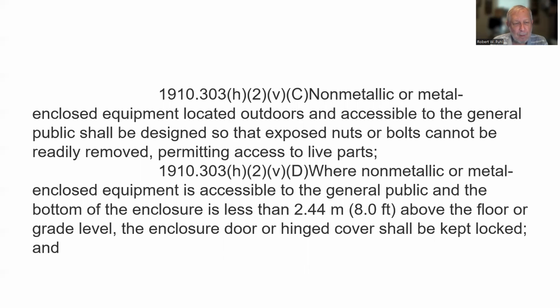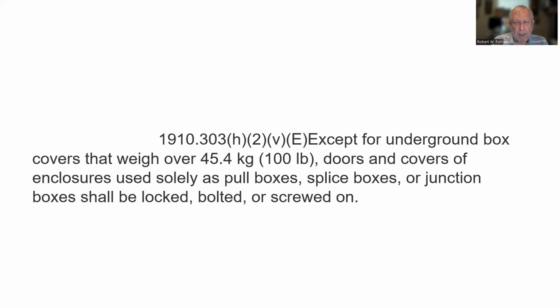Where non-metallic or metal enclosed equipment is accessible to the general public and the bottom of the enclosure is less than 8 feet above the floor or grade level, the enclosure door or hinge cover shall be kept locked, and except for underground box covers that weigh over 100 pounds, doors and covers of enclosures used solely as pull boxes, splice boxes, or junction boxes shall be locked, bolted, or screwed on. It weighs 100 pounds, so don't worry about it.